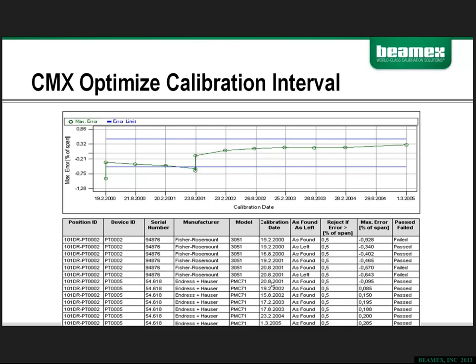Okay, so when it was initially put into service, the initial calibration on it at the same tolerance of 0.5% of span was very good, 0.095, which is just shy of 0.1%. So if you look at the history of this particular sensor over time, yes, there was some drift, but it was very insignificant. It went from 0.085 to 0.15 to 0.195 to 0.188, 0.2, and 0.285. So in terms of drift, that's very minor.